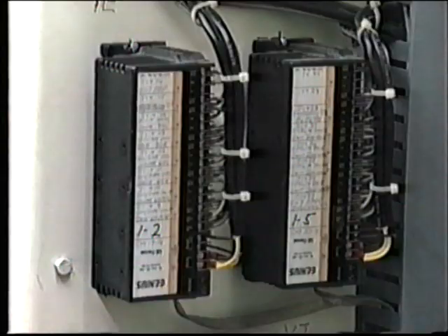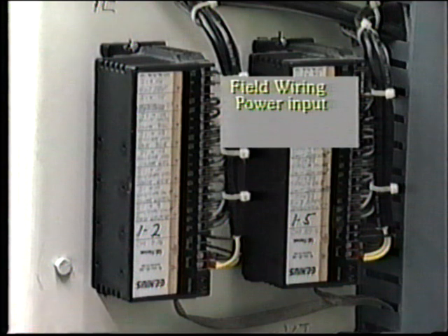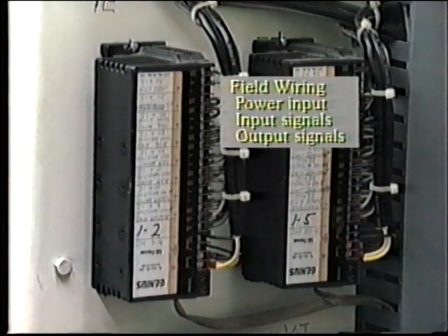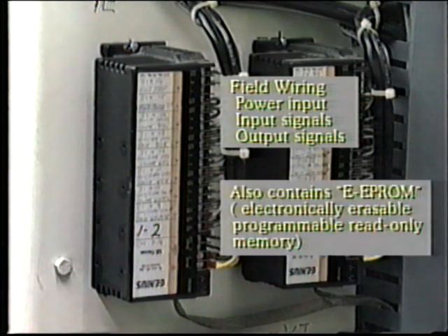But just as important as this extended capacity is the fact that the block itself contains a certain amount of processing capability. The I/O block is actually made up of 2 parts, the terminal assembly and the electronic assembly. First, the terminal assembly is where the field wiring is connected. For example, power supply to the block, input signals to the block, and output signals from the block. Located within the terminal assembly is the EEPROM, that is the electronically erasable programmable read-only memory. The program in this memory can be changed by commands from either the CPU or by a handheld monitor, which we'll look at in a moment. As you will remember, the EEPROM retains its memory even during loss of power.